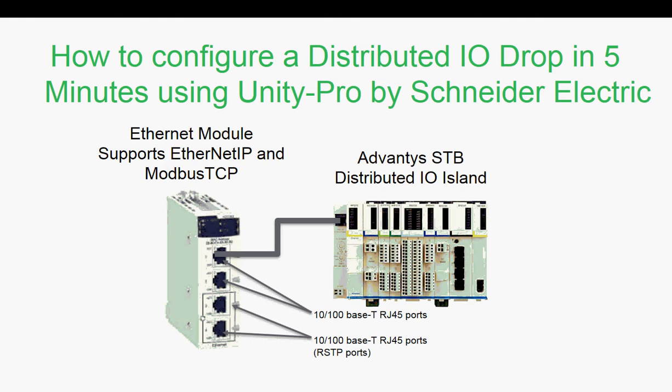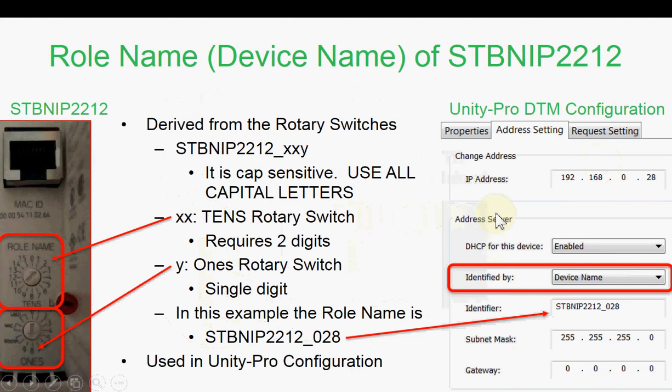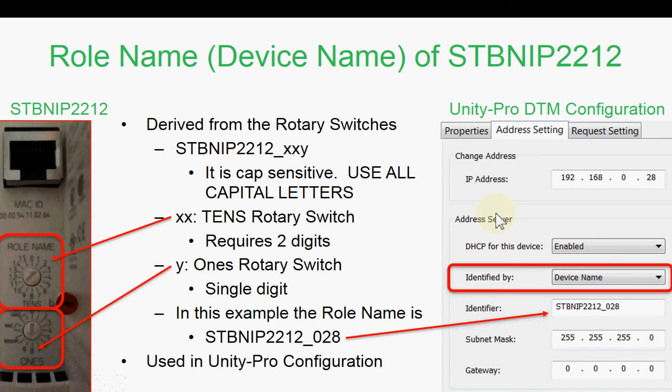We will use the DHCP server built into the Ethernet module to assign the IP address of the Advantys island. The most important thing when configuring the DHCP server is the name. It has to match exactly.